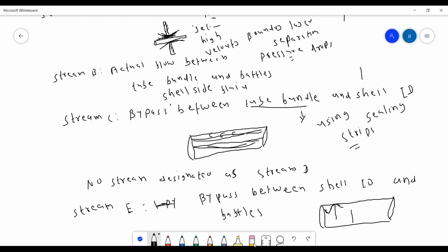Now the actual flow should be like this: fluid flows across from one baffle to another baffle. We also have baffles here, and here. So the actual flow is like this, this is the real flow, where we have tubes like this, and the shell side fluid must be in direct contact with tubes.